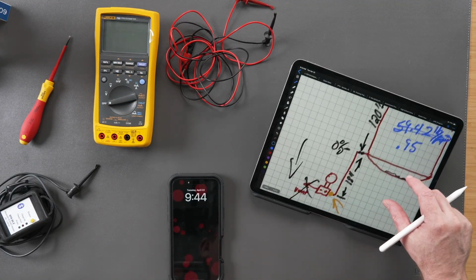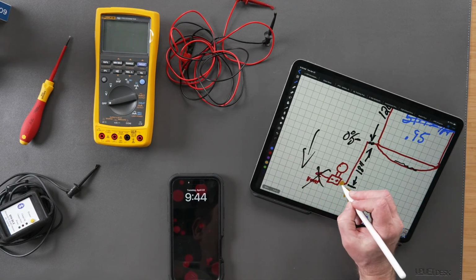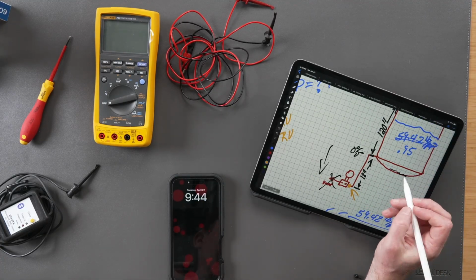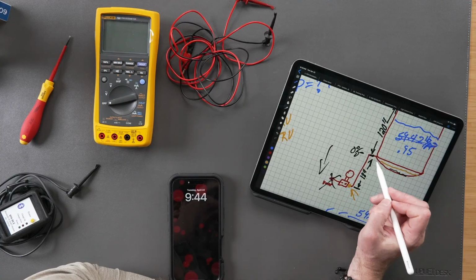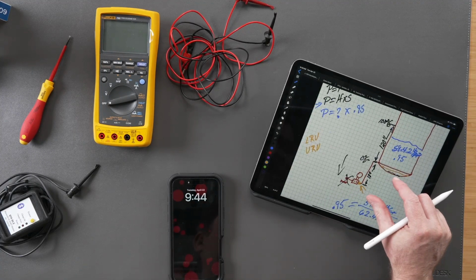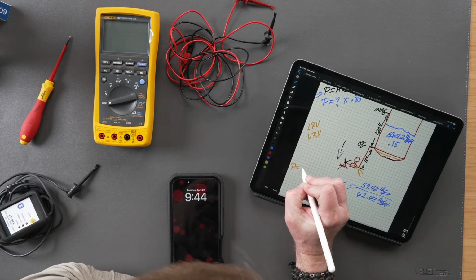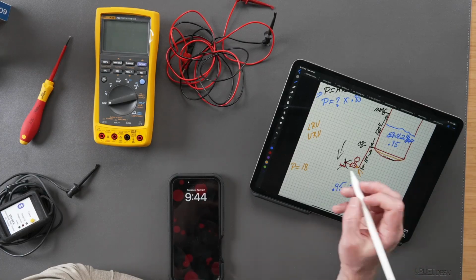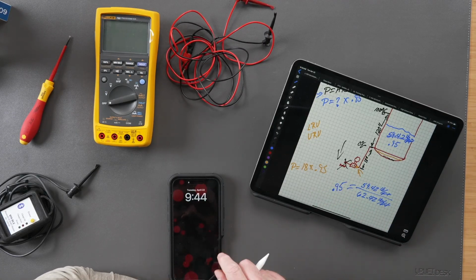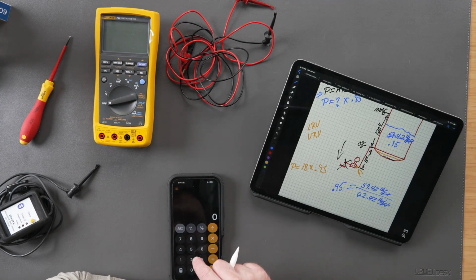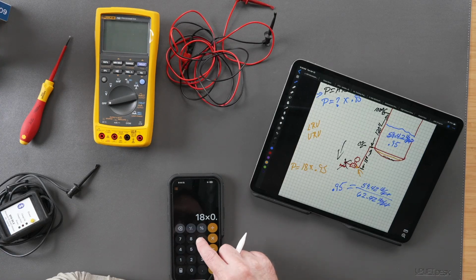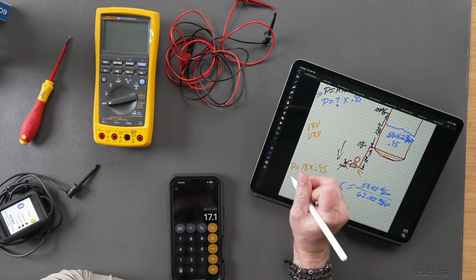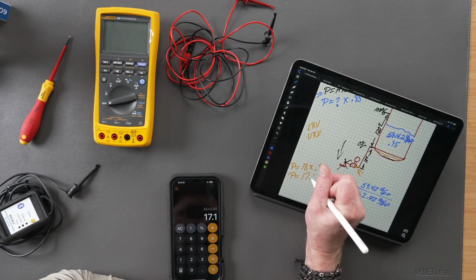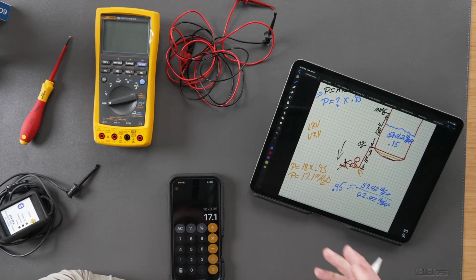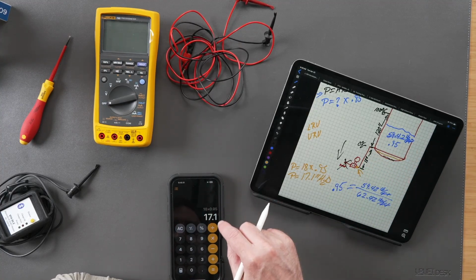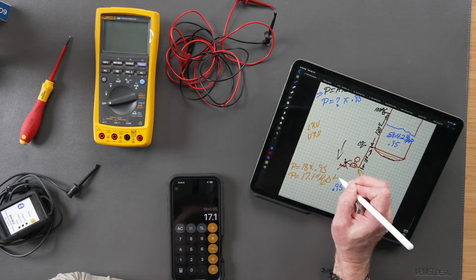So let's start with our LRV. How much pressure is going to be exerted right there? If I empty this vessel out to this point, how much pressure is going to be exerted on this cell? Pressure is equal to a height of 18 inches times a specific gravity of 0.95. So 18 inches times a specific gravity of 0.95 gives me a pressure of 17.1 inches of H2O. That's how much pressure is exerted on that cell when the tank is completely empty, which gives me my LRV value.